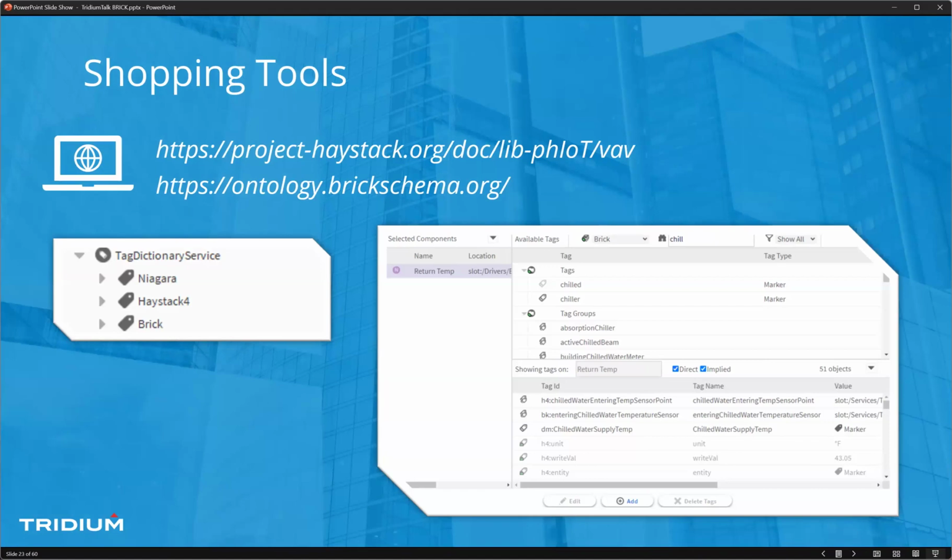And there's a whole standard of RDF on how that file is done. So there's lots of standard organizations trying to make a unified way of doing an ontology. Now, when Brick was first introduced, Haystack was the only ontology out there that was widely used. Haystack 4 was introduced to do more of what Brick was trying to achieve. So these actually work hand in hand, but you need to understand that they're attacking the same problem. Haystack 4 has the ability for groups and relationships, and Brick does the same thing, but it's all about how to make something that a machine can understand the context of who you belong to, right? And who did I come from, and how do I work within that model?